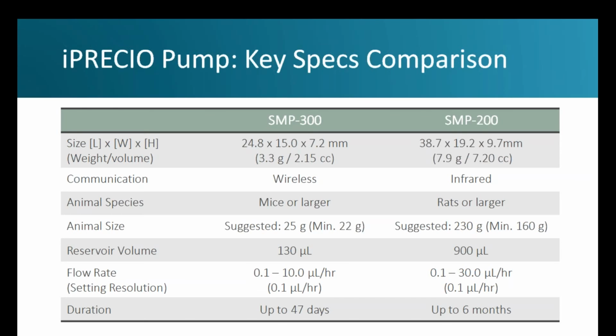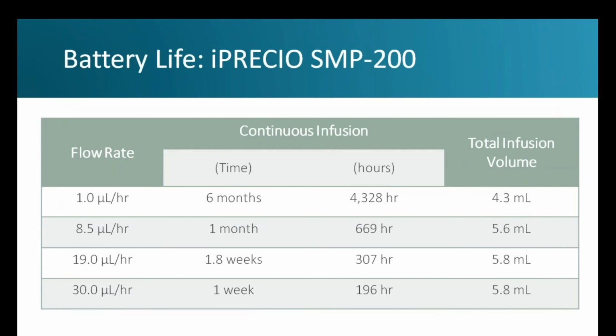The SMP 200 pumps are programmed by infrared communication with flow rates up to 30 microliters per hour, and the maximum duration possible is 6 months at the low flow rates. In fact, the duration of the pump is dependent on battery life. The SMP 200 pumps can deliver up to 6 months when programmed to deliver at 1 microliter per hour. As you can see in the table, the battery life is significantly reduced with the faster flow rate. So at 30 microliters per hour, you get about 1 week of battery life.